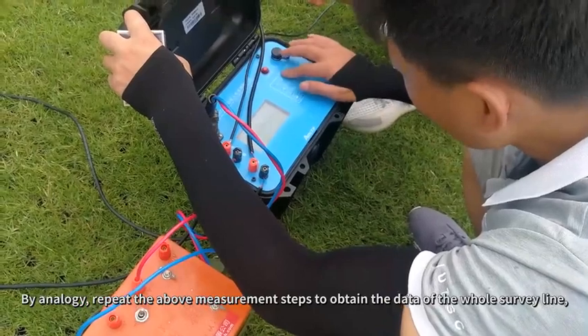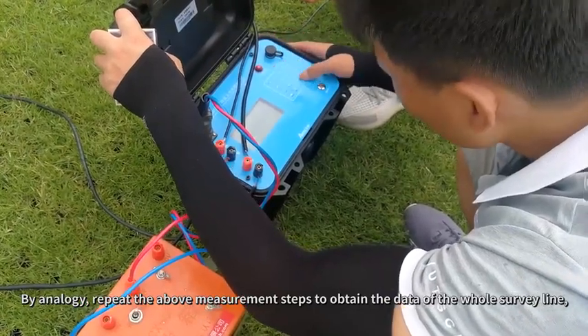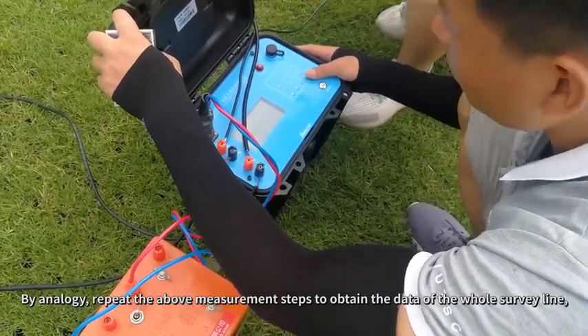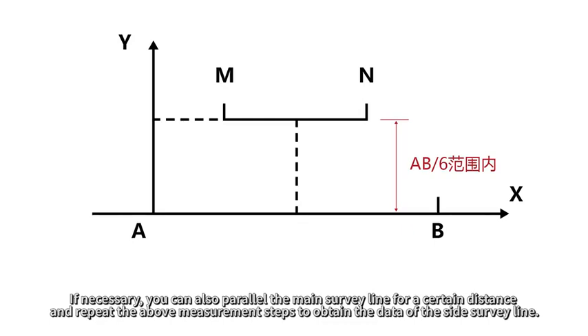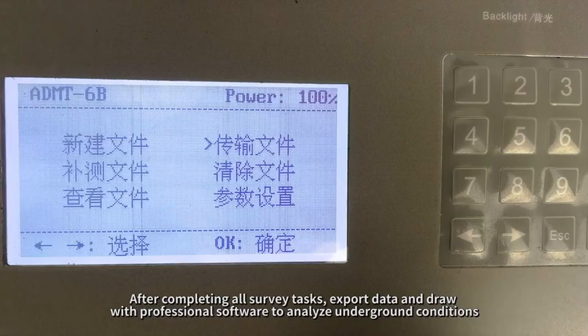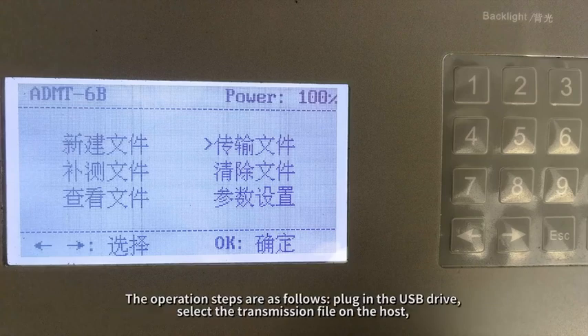By analogy, repeat the above measurement steps to obtain the data of the whole survey line. If necessary, you can also parallel the main survey line for a certain distance and repeat the above measurement steps to obtain the data of a side survey line. After completing all survey tasks, export data and draw with professional software to analyze underground conditions. The operation steps are as follows.